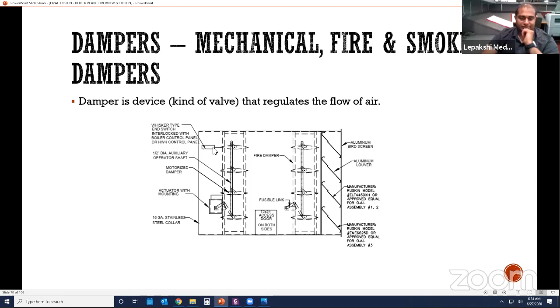So this is the damper, and that's the damper motor. You can see they can open and close with this motor. Now the boiler is telling this motor to open up the damper, but the boiler doesn't know whether this damper is actually open or not.